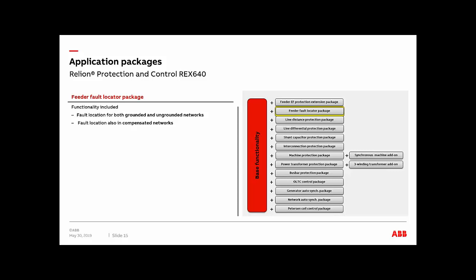Then we have the package that we call feeder fault locator package. Simply, this package will give you a fault location both for grounded and ungrounded networks, and also in compensated networks. It simply provides impedance-based fault location, and it is designed for radially operated distribution systems mainly. It will give you an estimation of the physical location of the fault based on the parameters of the line. As long as you know your impedances and resistances and reactances, you can input the data to the relay, and it can give you an estimation of the physical location of the line faults.